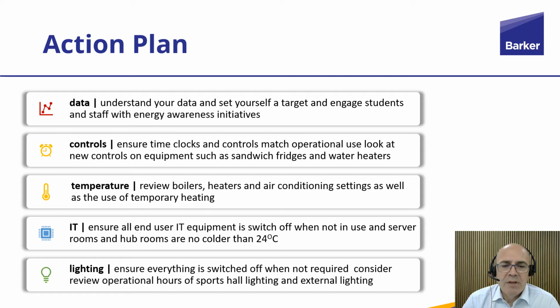First of all, when you've got that data, look at your controls, look at when your time clocks are set, look at how you are using your building, and does that match against how your heating is programmed. It's key to understand when you are in the building and when your heating is coming on and when it's going off.